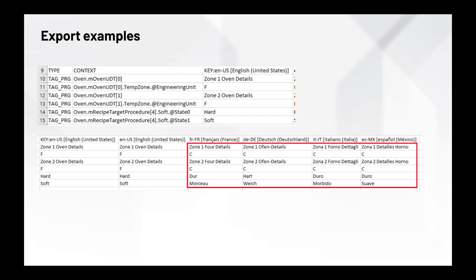Let's examine the extended properties export. The items shown at the top are the English text for the objects that are shown on the 07 miscellaneous display in FactoryTalk View Machine Edition. Below is the translated text for those same objects. Each translation is entered under the appropriate language code header. Once the translations are complete, the text file is imported back into the Studio 5000 Logix Designer file. The file is then downloaded to the Logix processor to complete the process.